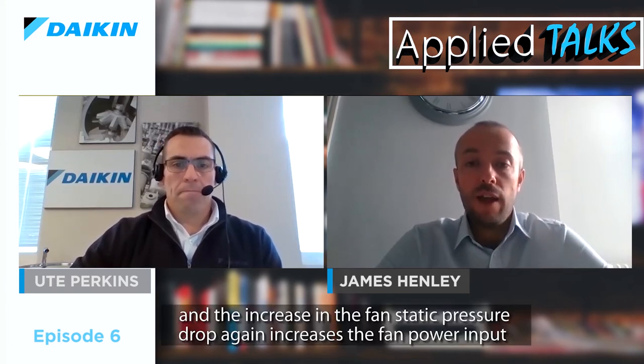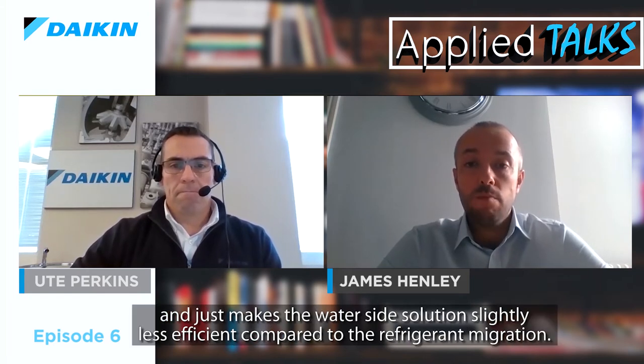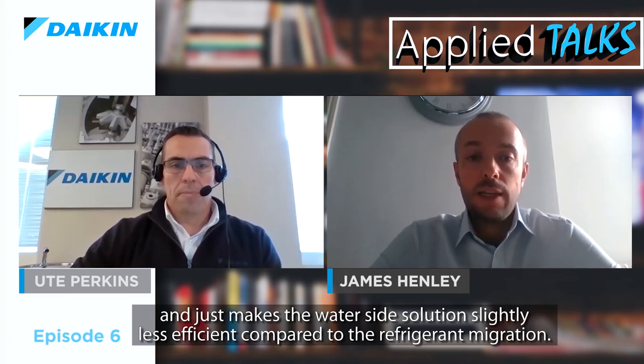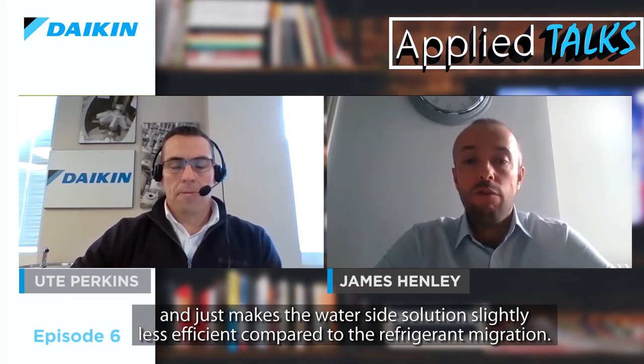Also, considering the additional free cooling water coil pressure drop increases the pump power in the system, and the increase with the dual coil in the fan static pressure drop again increases the fan power input and just makes the water side solution slightly less efficient compared to the refrigerant migration solution.